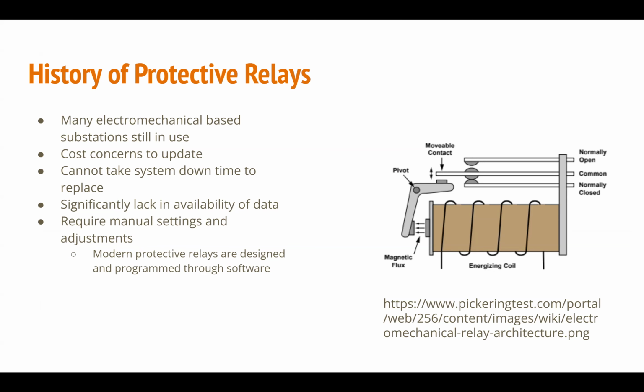Essentially we have a couple different types of protection equipment in the power industry. The oldest stuff still in active use is electromechanical based protection. Many of you have probably taken the PLCs course at UMaine, where you used ice cube relays - that's basically what we're talking about with electromechanical based relays. The electrical concept is that you have a little arm on a pivot, and contacts that get connected or disconnected when this arm is pivoted.